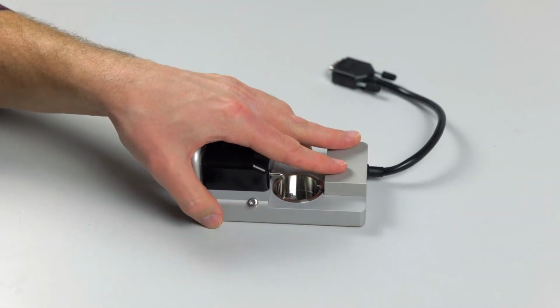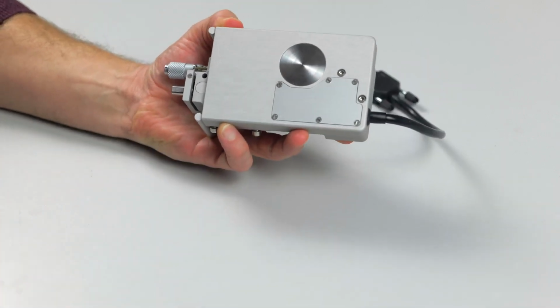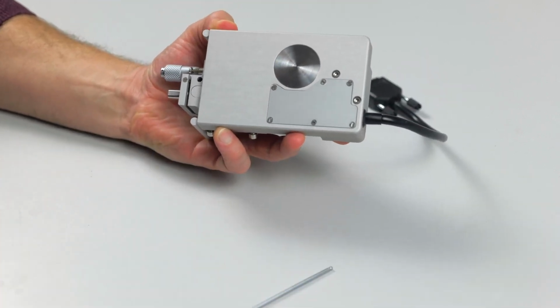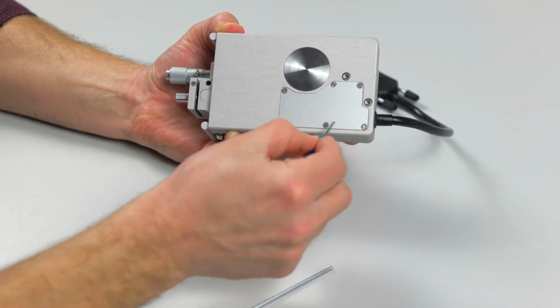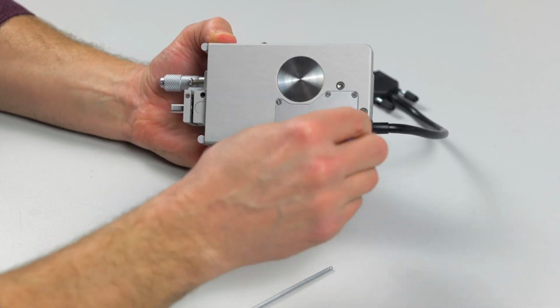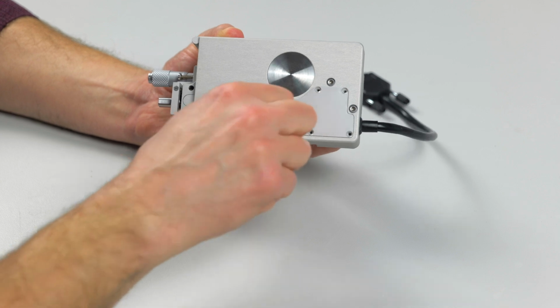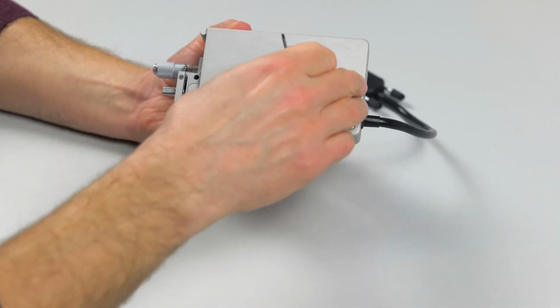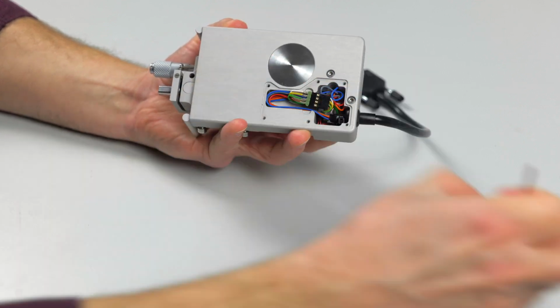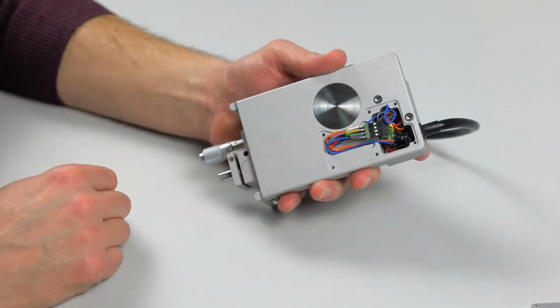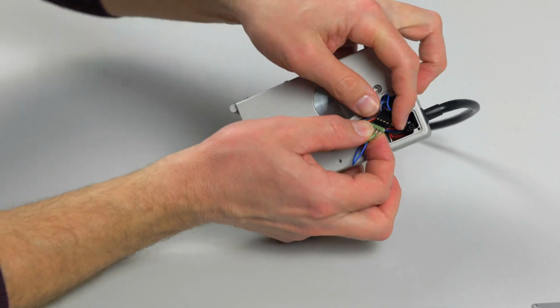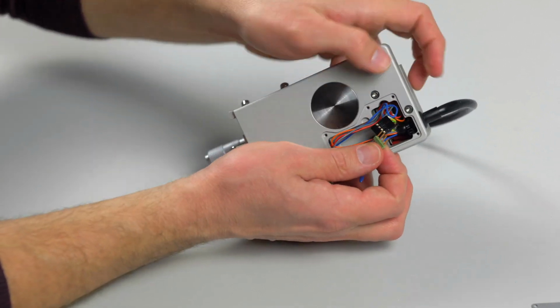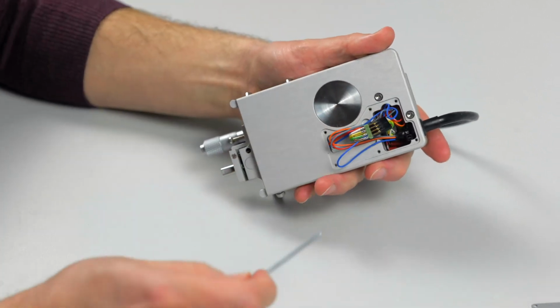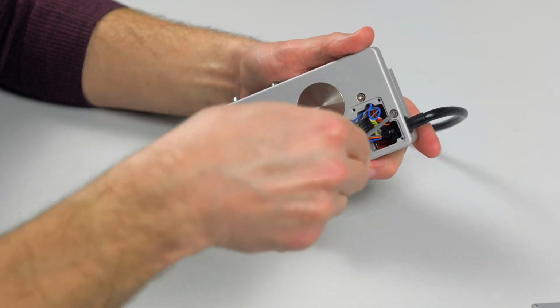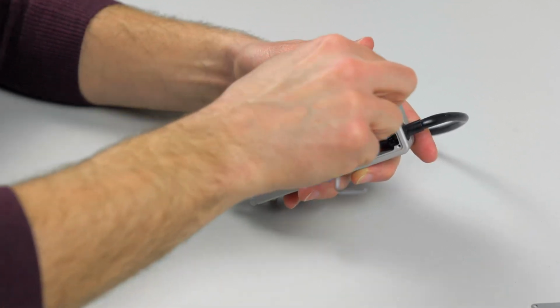To remove the transducer, we'll flip the chamber over and you will loosen the 6 screws here covering the bottom plate. Then remove the backing plate, keeping the grease side up. Once the backing plate is removed, carefully disconnect the wire. You then need to remove the 2 Allen screws using the 2.5mm Allen key that came with your system.